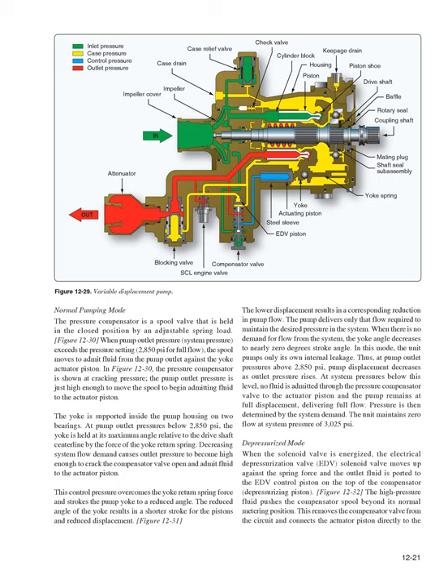Figure 12-31: the lower displacement results in a corresponding reduction in pump flow. The pump delivers only that flow required to maintain the desired pressure in the system. When there is no demand for flow from the system, the yoke angle decreases to nearly 0 degrees stroke angle. In this mode, the unit pumps only its own internal leakage. Thus, at pump outlet pressures above 2,850 pounds per square inch, pump displacement decreases as outlet pressure rises.